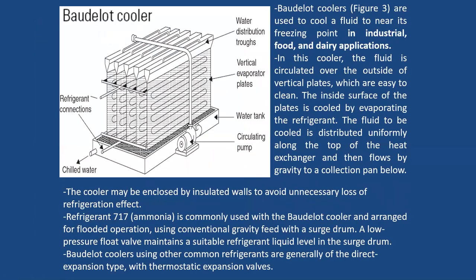This is a special type of cooler, which is called a Baudelot cooler. Baudelot coolers are used to cool fluid to near its freezing point. In industrial food or dairy applications, generally it is used. In this cooler, the fluid is circulated over the outside of vertical plates, which are easy to clean. The inside surface of the plate is cooled by evaporating the refrigerant.